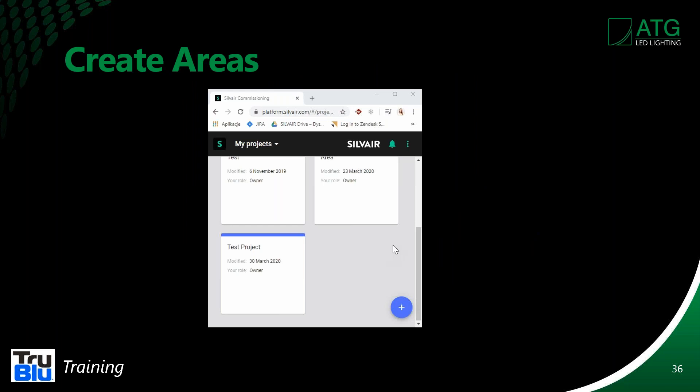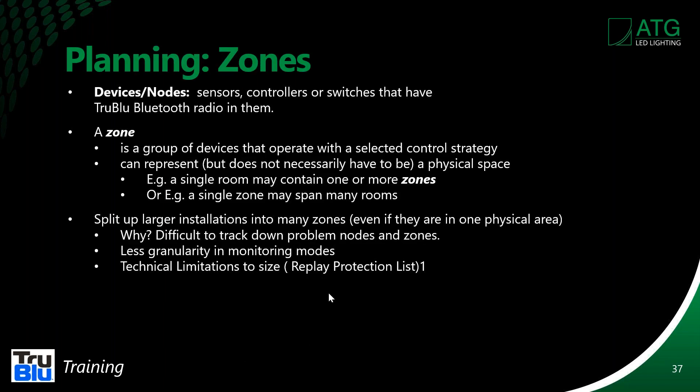You can create areas, give them a name, and then plan the zones. We have sensors, controllers, and switches. A zone is a group of devices that operate with the same control strategy — that's the main point to remember. All the fixtures in a particular zone are going to operate on the same control strategy. You can also split up larger installations into many zones.